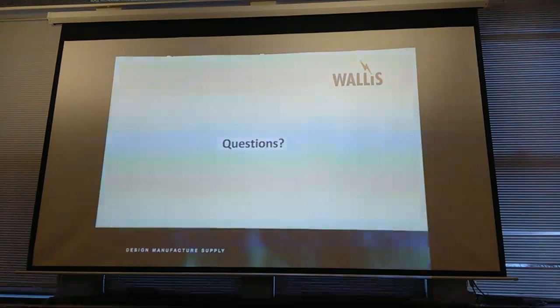Are there any questions? How do you determine the percentage of earth fault that goes through the feeder cable? It's down to cable type, cable impedance, whether it's trucks, whether it's 3-core, whether it's lead sheath, whether it's pill, whether it's steel wire armour. At the back of S34, this document, get your hands on, it's fantastic. It's a little light reading for the night time. There are tables and tables and tables of mutual impedances. At the back of there are formula for different configurations of earth systems. You can choose which formula fits your side, and you can just work through the calculations.